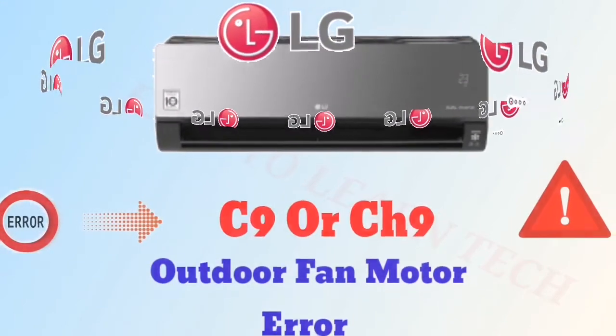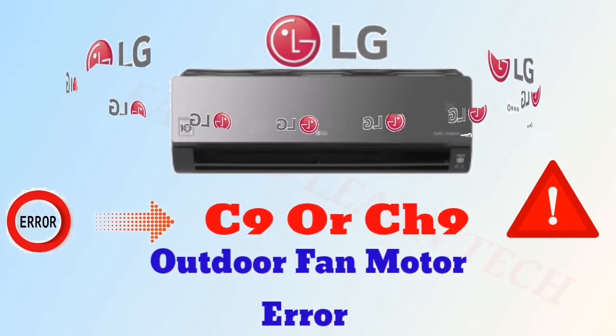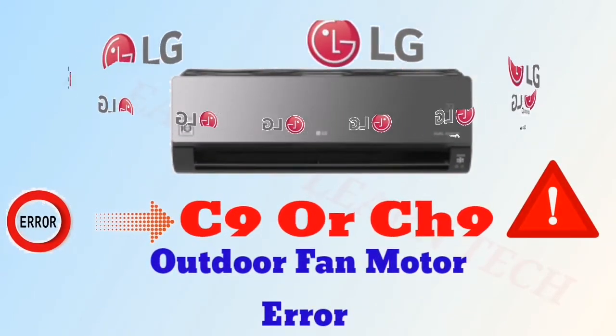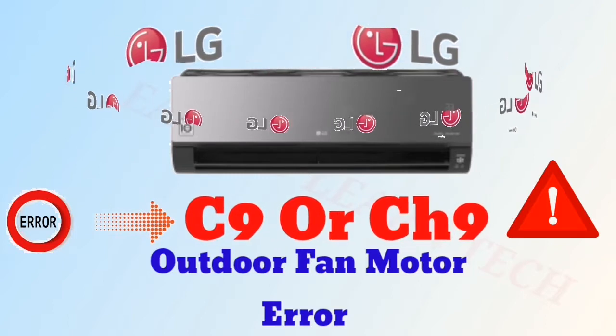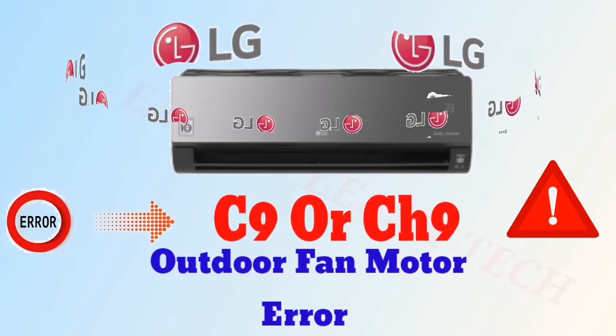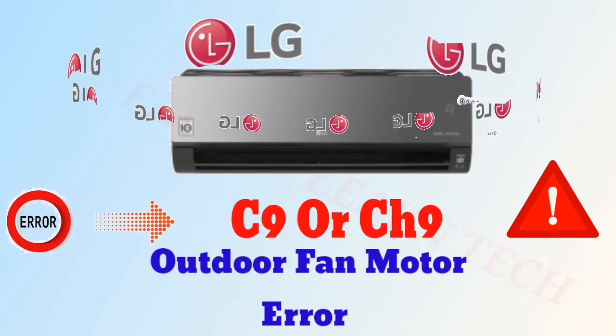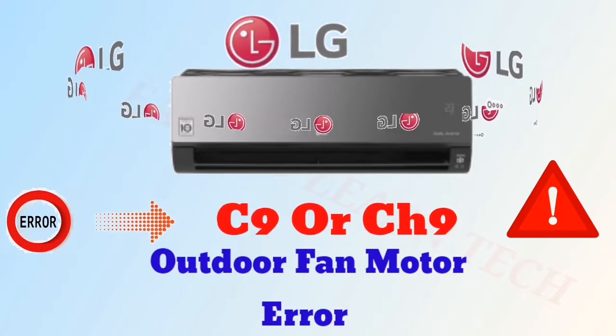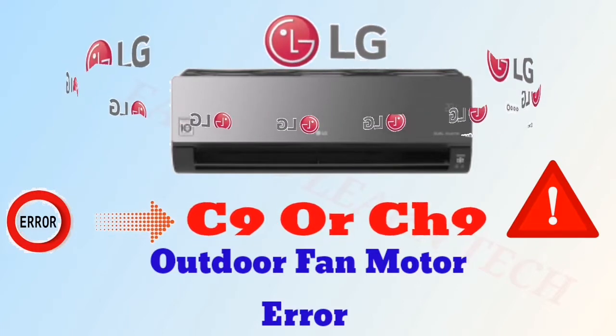Let's see the next error code. When you see the error C9 or CH9, it means outdoor fan motor error. This error is similar to C8, the indoor fan motor error. You have to follow the same process as for C8 and you can solve this issue, and your unit will be in working condition.